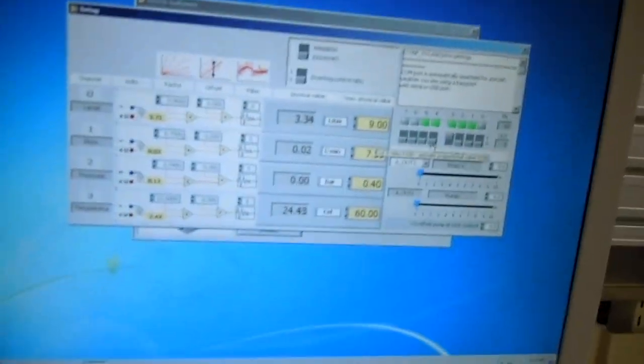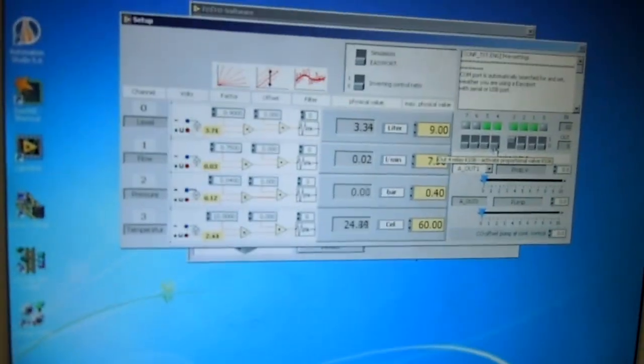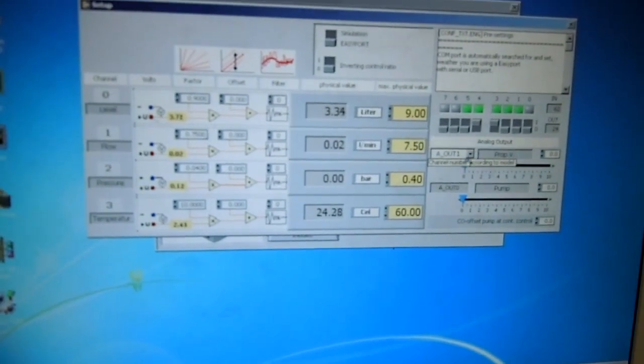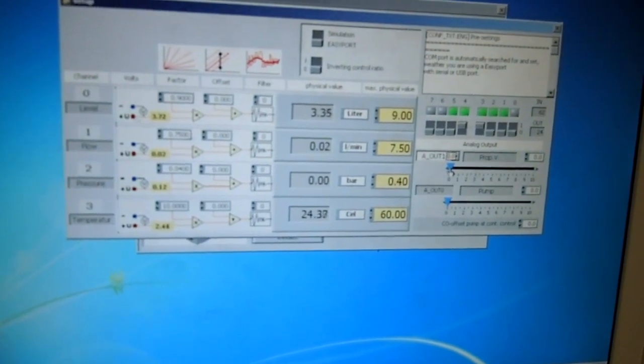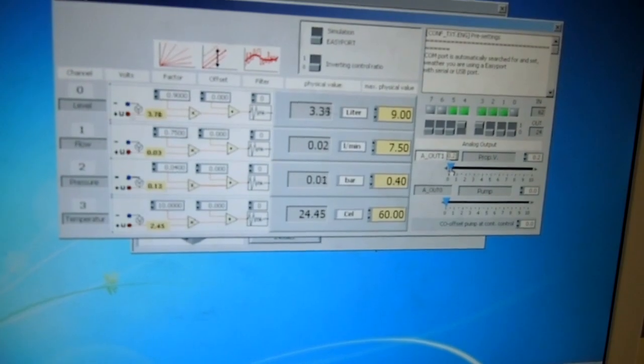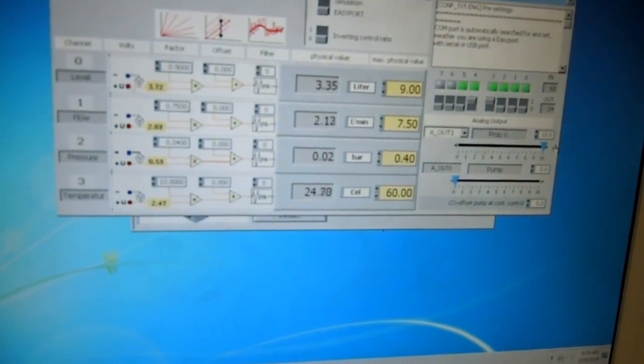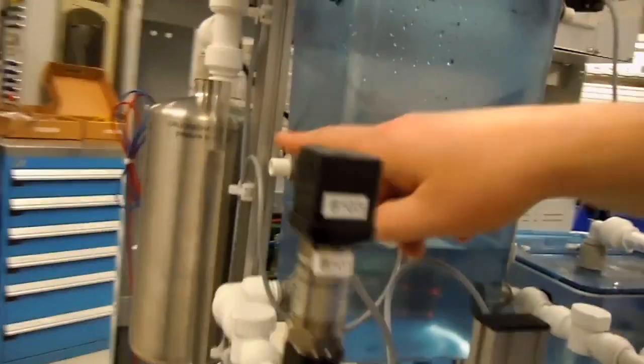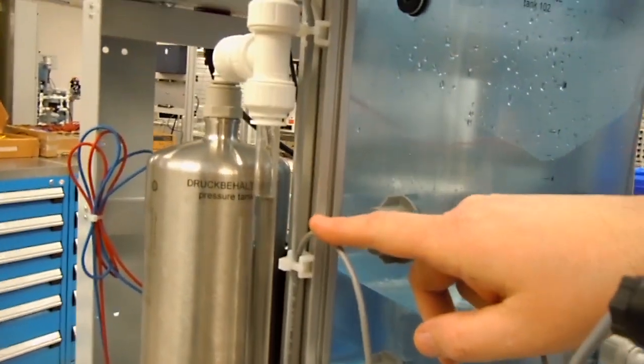So back over to the screen, one of the things I have to do is to enable the proportional valve, and it's done with bit 4. So it's now enabled, and then if I move this slider, it's going to open the valve, and I'm going to open it 100%. So back to the station. Now have a look at the level in that plastic tubing. It's starting to go up.